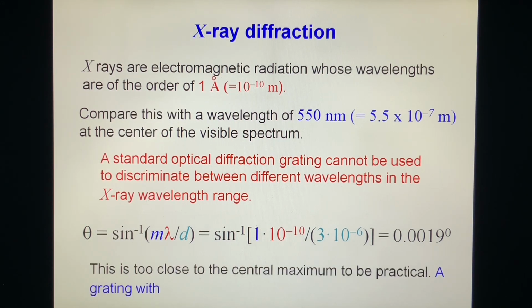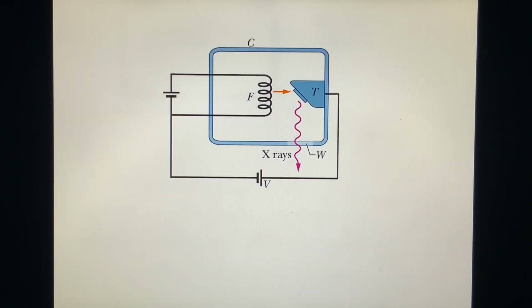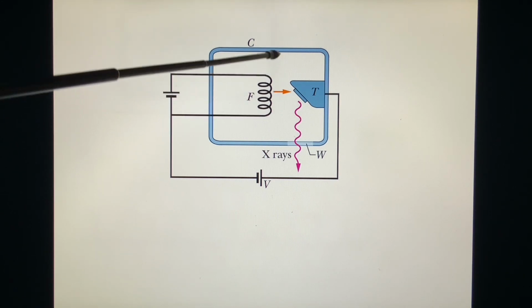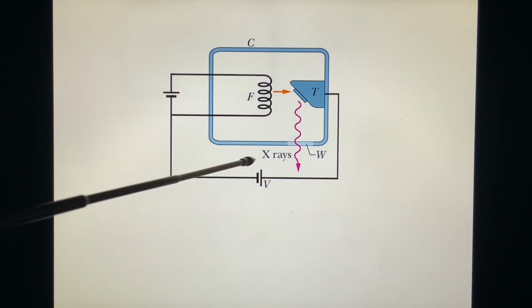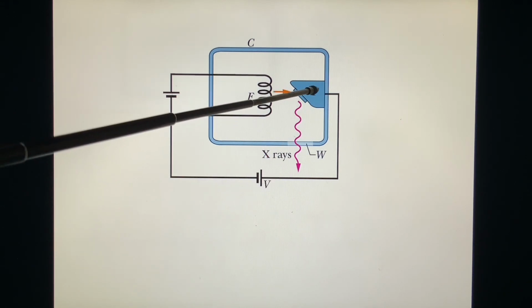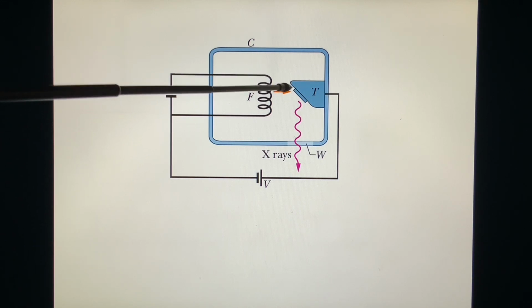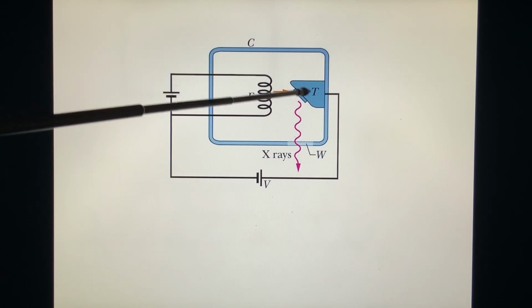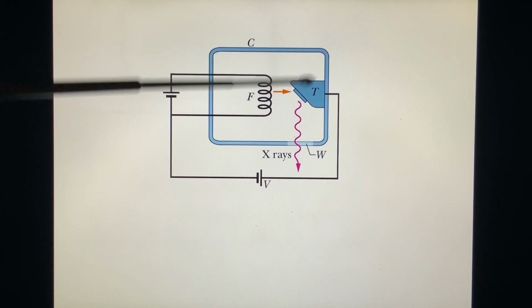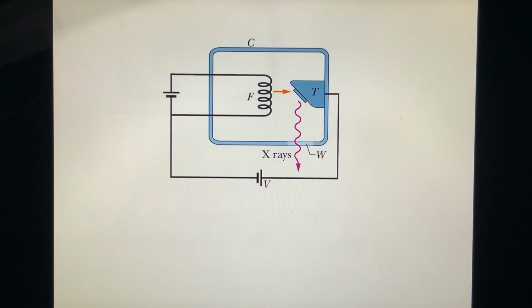Well, where to find it? Let's see how X-ray is emitted. This is the heater, a resistance. We apply a current, so it is getting heated, and an electron inside escapes from it. Once it escapes into the space, there is a huge voltage applied. So this is positive, so the electron hits the positive electrode, and this is a metal, tungsten. And when the electron hits the tungsten, the tungsten will emit X-rays.